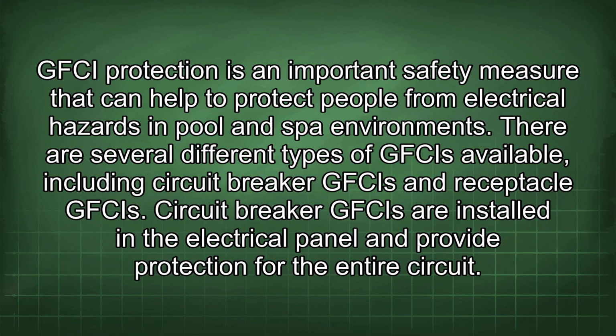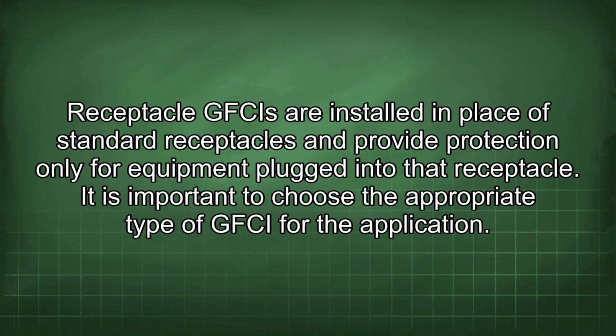GFCI protection is an important safety measure that can help to protect people from electrical hazards in pool and spa environments. There are several different types of GFCIs available, including circuit breaker GFCIs and receptacle GFCIs. Circuit breaker GFCIs are installed in the electrical panel and provide protection for the entire circuit. Receptacle GFCIs are installed in place of standard receptacles and provide protection only for equipment plugged into that receptacle. It is important to choose the appropriate type of GFCI for the application.